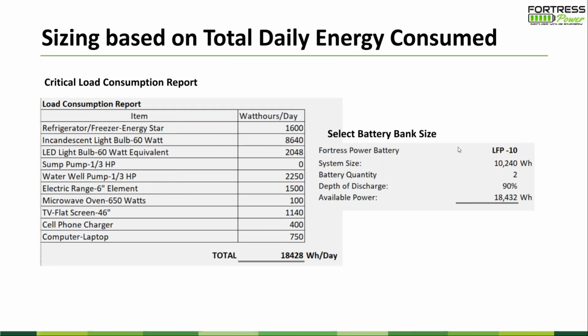A quick recap: we need to look at whatever we put on the critical load - usually a well pump, maybe a water heater, your phone charger, anything you want to use when the power is off. Those we call the critical panel. For example, here we calculate 18 kilowatt hours per day. That's where we start sizing our battery bank - we say okay, at least we need that much energy.